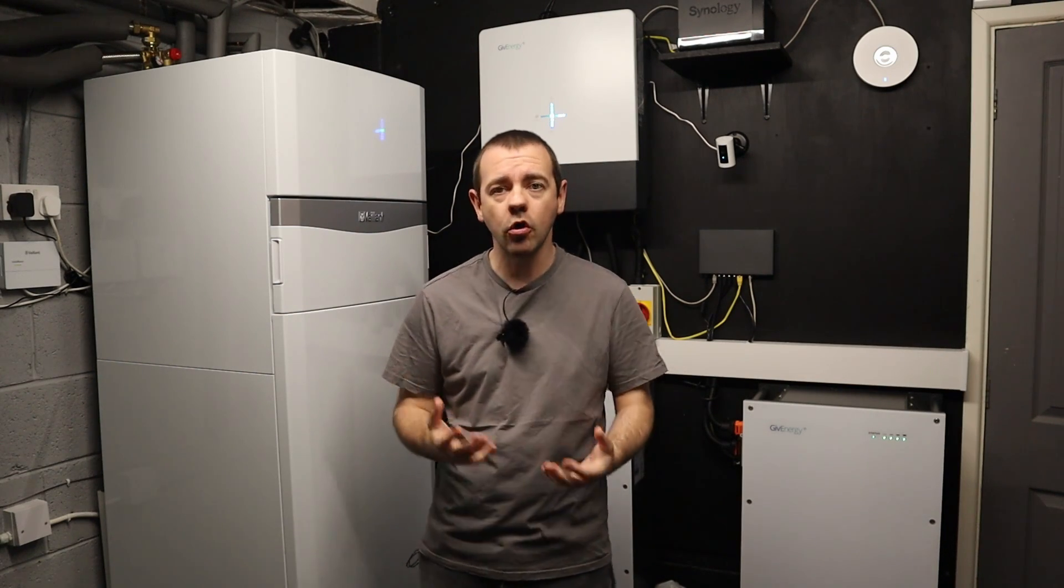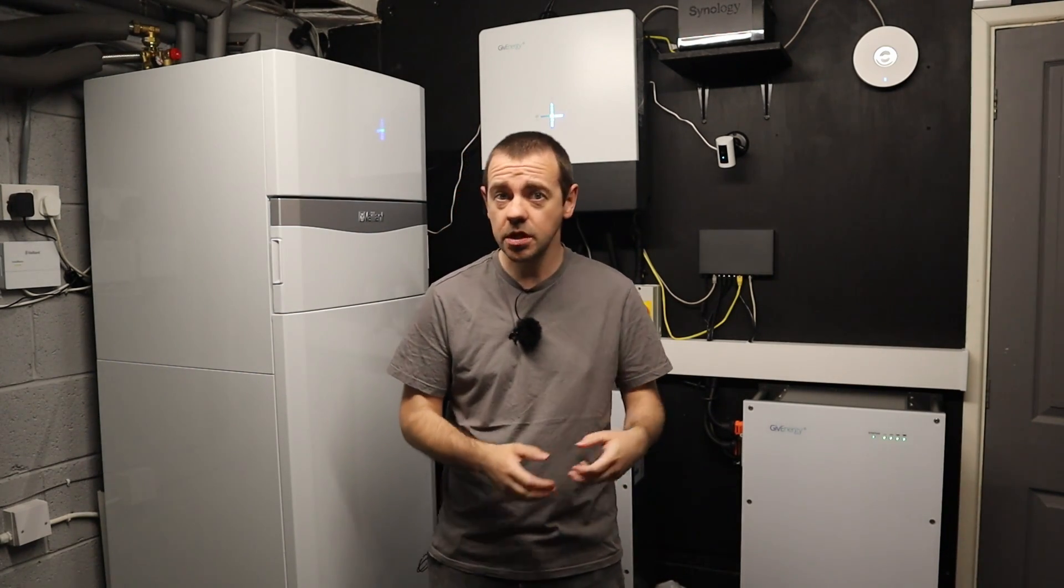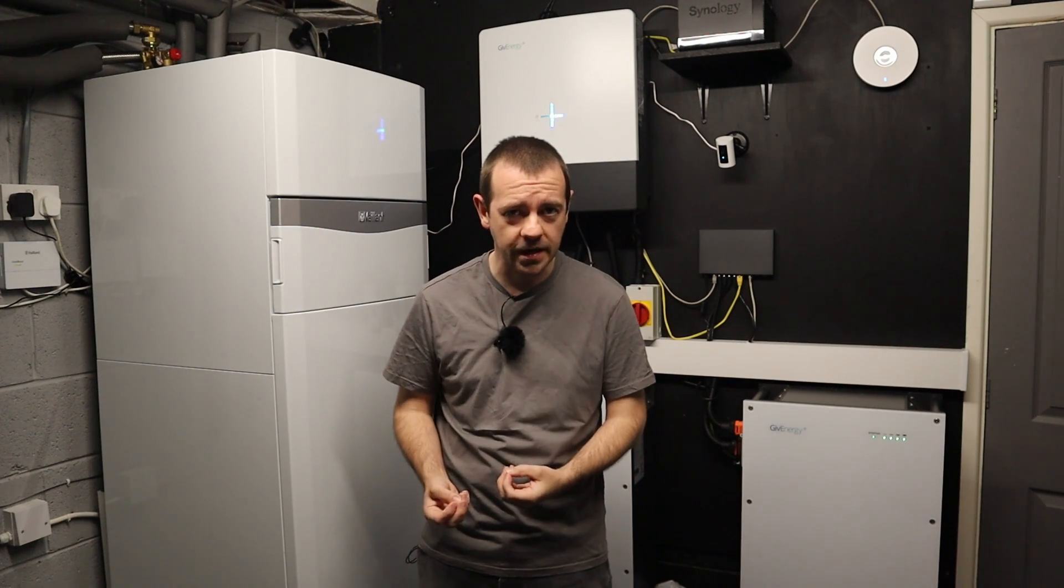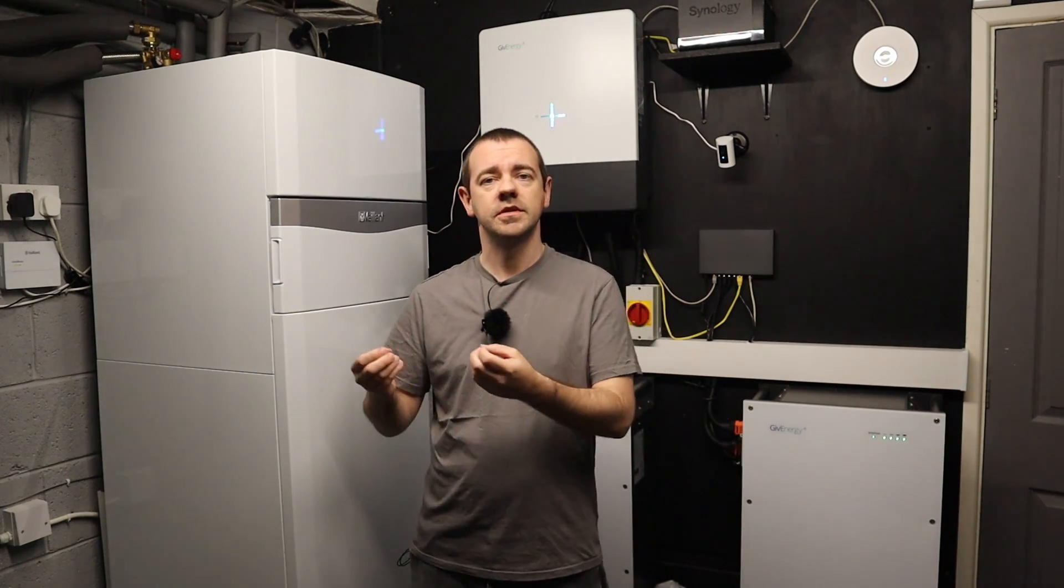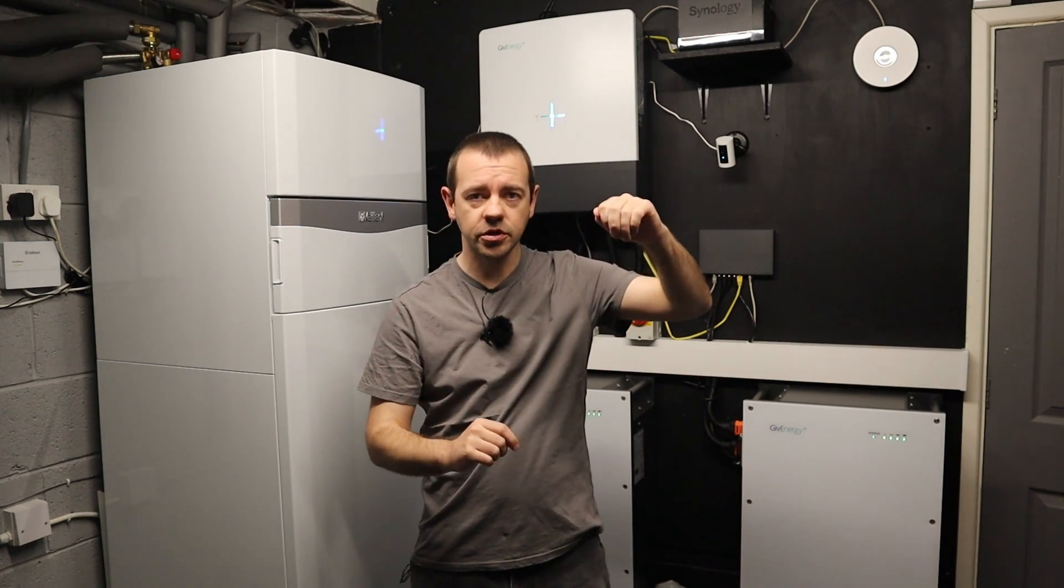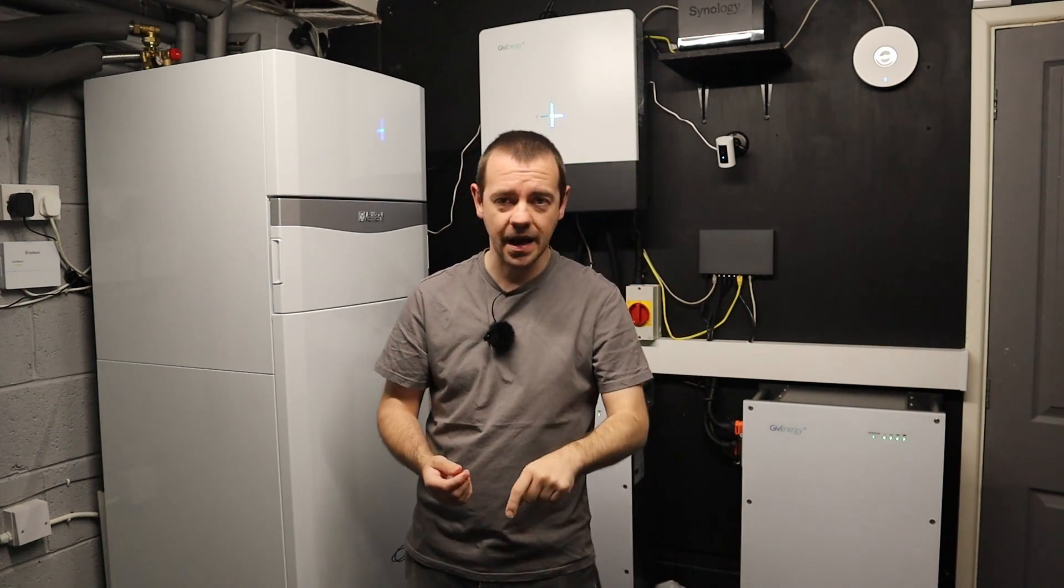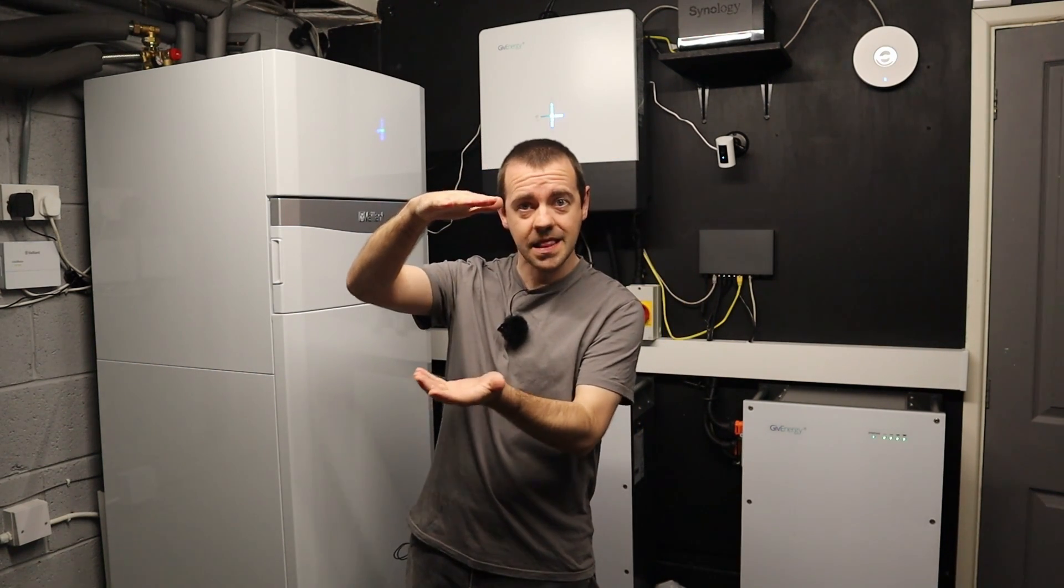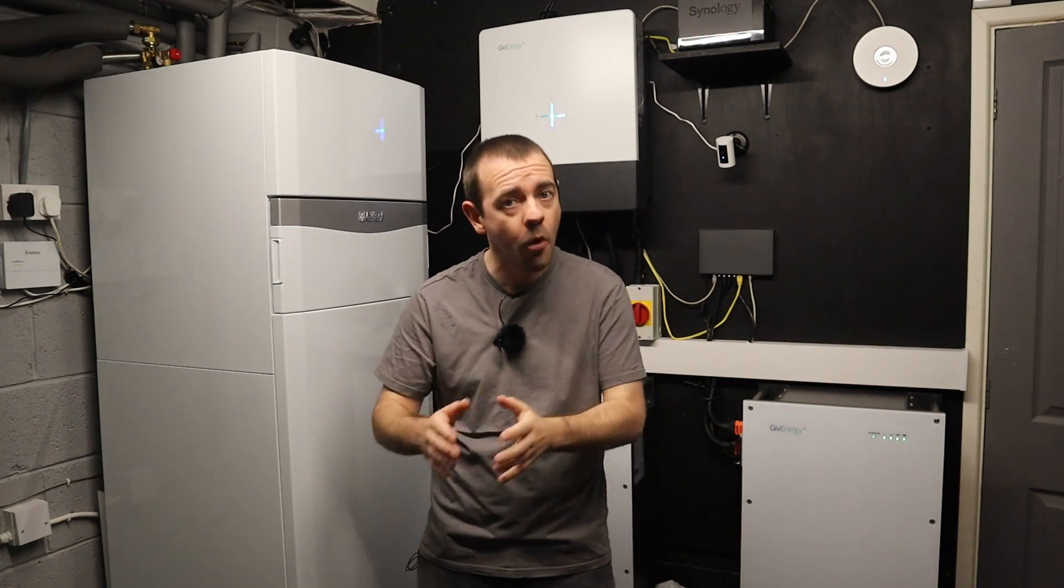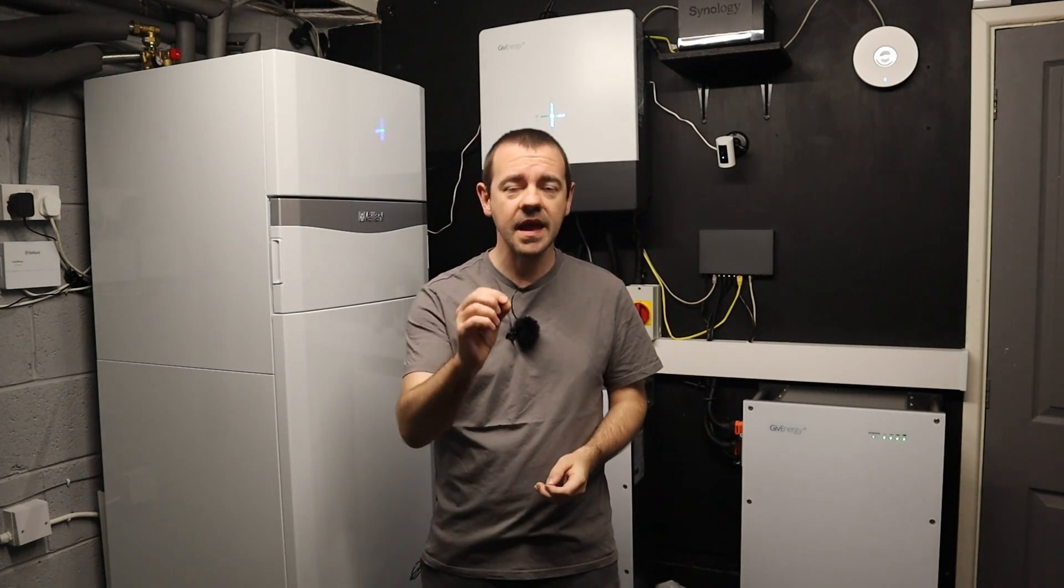So this whole thing of you have to leave them running 24 hours a day, which is a load of rubbish, doesn't mean that it will be running at 2.6 kilowatts for 24 hours - no, it's not like that at all. The reason it has to be on all the time isn't because you have to, it's because you want to. That's the most efficient way of doing it. Efficiency equals savings. So think of it like a bucket with a hole in the bottom. It's trickling out water and you want to put in the water at the top of the bucket at the same rate it's coming out. So effectively the water level in that bucket never drops. You're putting the heat in at the same rate the house is losing it.